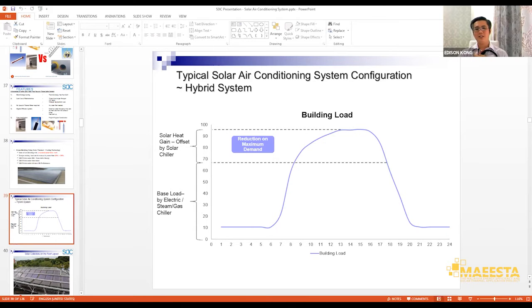The startup is automated. It will need a certain startup period, but it's not long, just a couple of minutes. The system is programmed so that once the sun rises and we have solar energy, we scan whether the temperature we can harvest is higher than the temperature in the tank. The circulation pump will run one round, then we measure the temperature coming back from the solar collectors. If it's still lower than the tank temperature, the pump will stop for another duration, around 20 minutes or so.